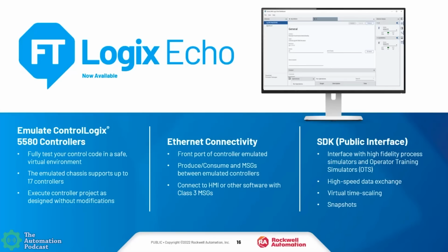It also does have an SDK that's different than the SDK we just talked about. This one is Echo specific and included. You have high speed data exchange, virtual time scaling, and can even do some operator training with various simulators as well. So Logix Echo is currently supported with version 33 and above. That is something to be aware of. And I don't think we said it, so for those listening, this is 5580 controllers. If you have 5570s, Logix Echo is for 5580 controllers.